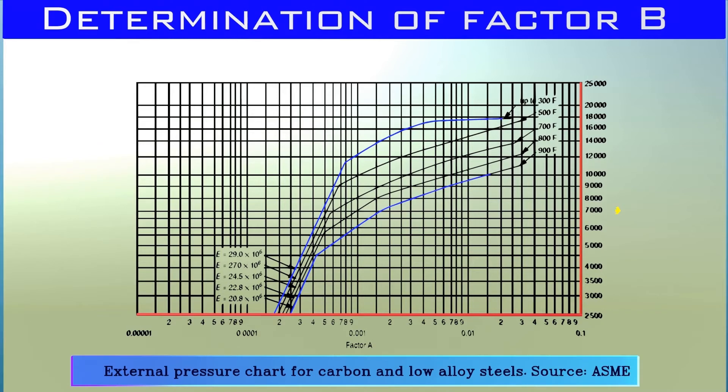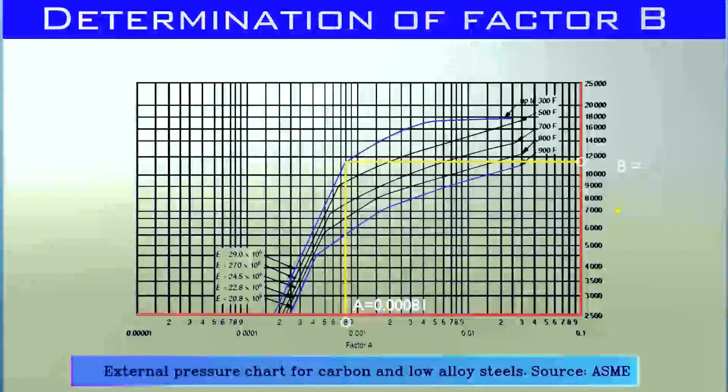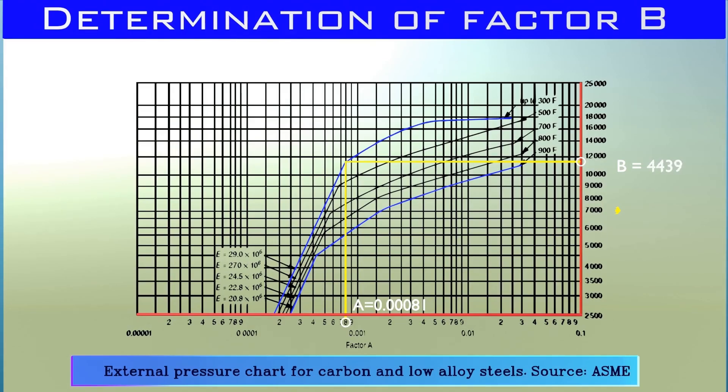We will spot the value of factor A on the x-axis, that is 0.00081 as previously determined. We will take the line up to the operating temperature curve of the vessel and relative strength of the materials, and then to the axis of factor B. This will spot the value of factor B, which is 11,800 respectively.